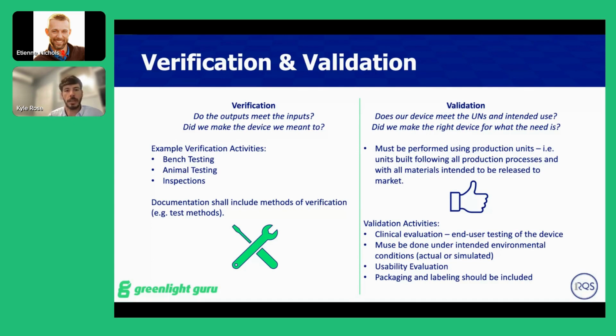Key thing with verification activities is it needs to be documented before we start testing on what is going to be done, how we're going to test it, and specifically what the acceptance criteria is. We can't go into a test just saying, oh, we're going to see what happens and then decide if it passes or fails. We need to have a clearly defined acceptance criteria and pass-fail justification before we start any of this verification testing. So all this internal bench testing should be formally documented with protocols. These protocols should be reviewed and approved internally, as part of your quality system activities, before you start testing.